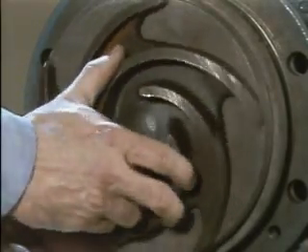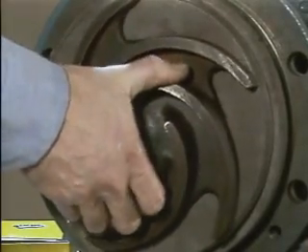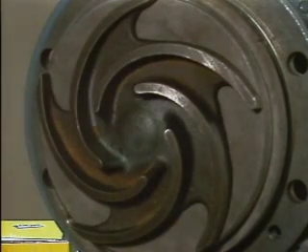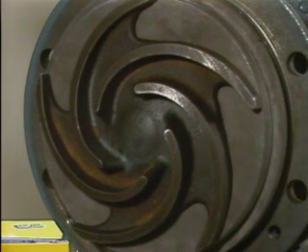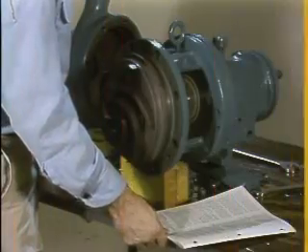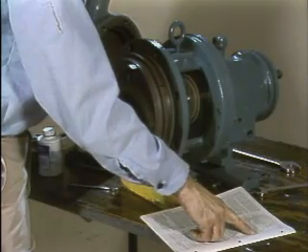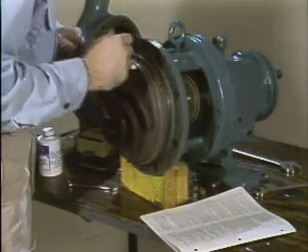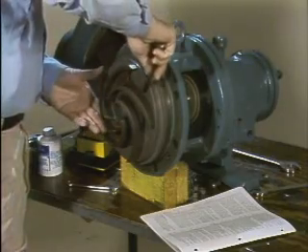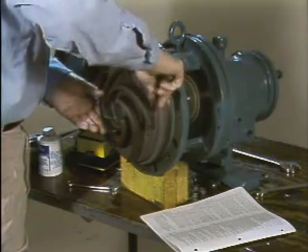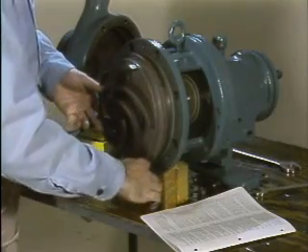The clearance between the impeller and the backplate must be measured to make certain that the impeller is positioned correctly. The impeller holds the shaft sleeve in place, so if the impeller is out of position, the shaft sleeve and the mechanical seal components on the sleeve could be out of position as well. And if these components are out of position, the mechanical seal could fail. To determine the proper clearance between the impeller and the backplate, the pump manufacturer's specification should be checked. Then the gap between the impeller and the backplate is measured with a feeler gauge, and this measurement determines if the impeller is positioned properly.